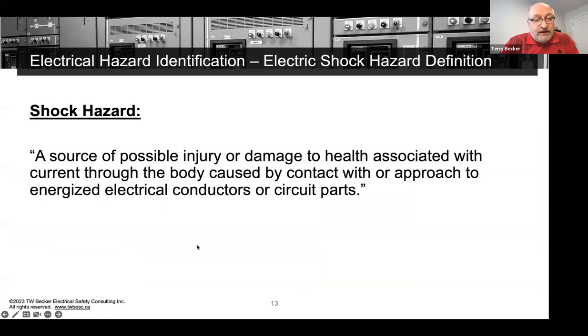So the definition of a shock hazard, and this is right out of 70E and Z462: a source of possible injury or damage to health associated with current through the body caused by contact with or approach to energized conductors and circuit parts, right? So that's it. You've got to make contact with a low voltage. You've got to contact it. But for high voltage overhead systems, distribution lines, substations, switch yards, you don't have to necessarily make contact. You get too close, the voltage is high enough, it'll arc through the air and it'll go through you to ground and cause a shock. Well, it'll probably be an electrocution at those high voltages pretty well instantly.